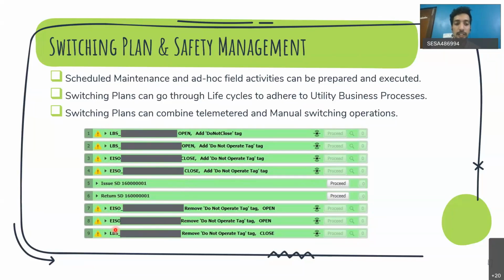Opening of earth switches and closing of load break switches - this switch could be remotely controllable, so the operator just opens it from the control center. Another may not be controllable, so he talks to the field crew on the phone and asks them to open it. Once opened, he manually updates the status. Everything is done in a coordinated way, and everything is recorded.